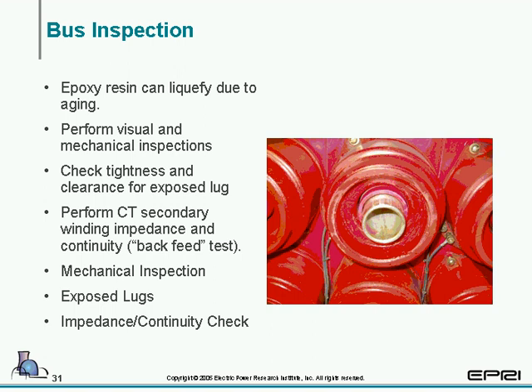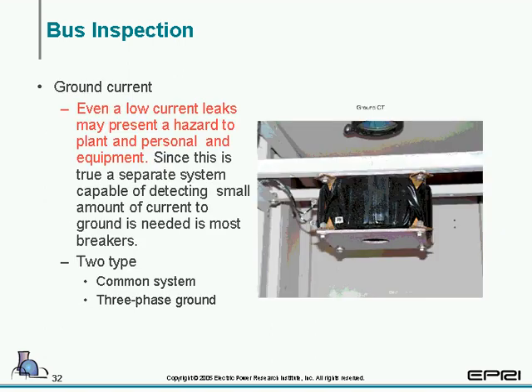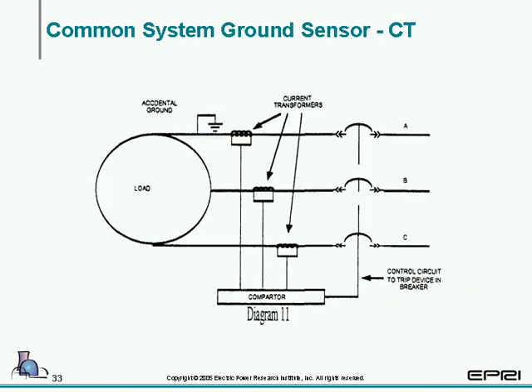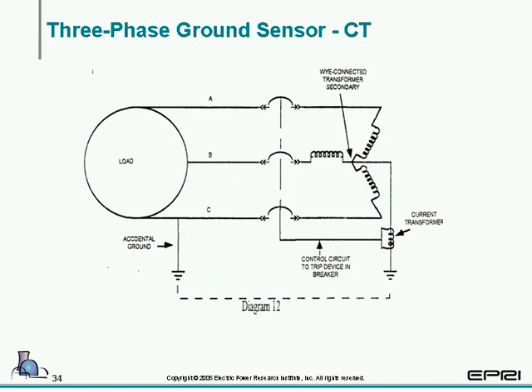CTs. If we look at CTs, you have to be careful because epoxy resin can liquefy over time. If you want to perform a visual inspection, check for tightness. You can perform a CT secondary wiring impedance and feedback test. The next one we'll take a look at is the ground transformer or ground CT. It's very important to keep in mind that even low current leakage may present a hazard to personnel. There are two common types. We're looking at a picture of one, and then a picture of another common type of ground sensor.